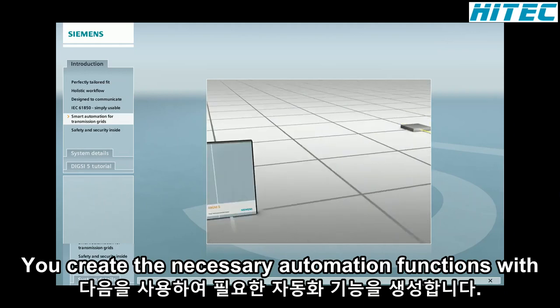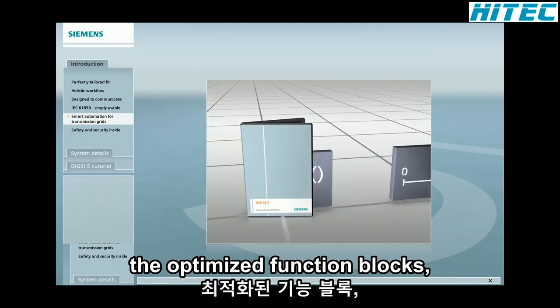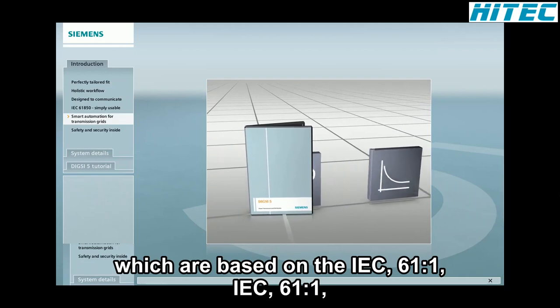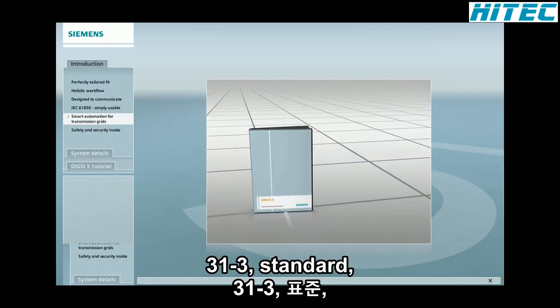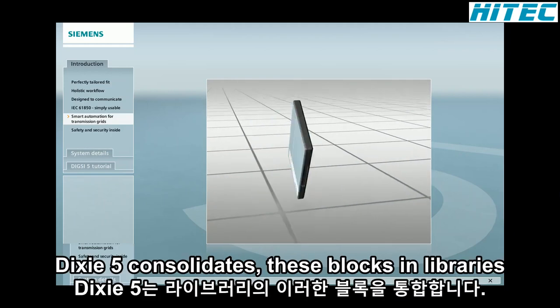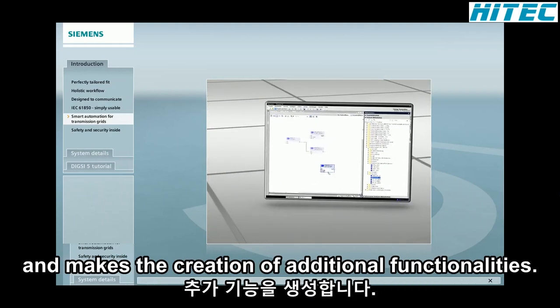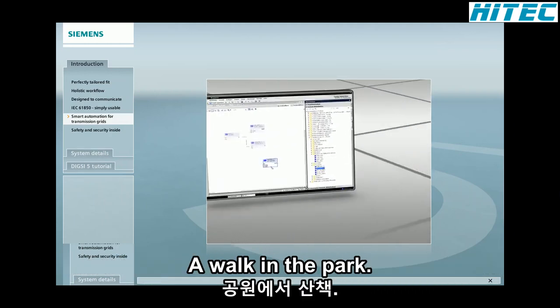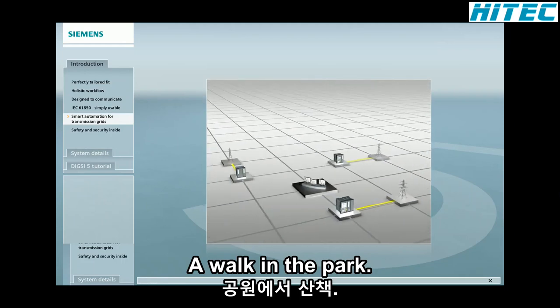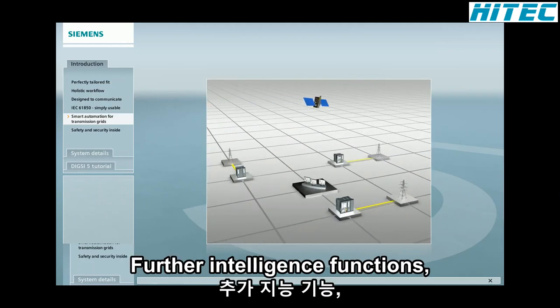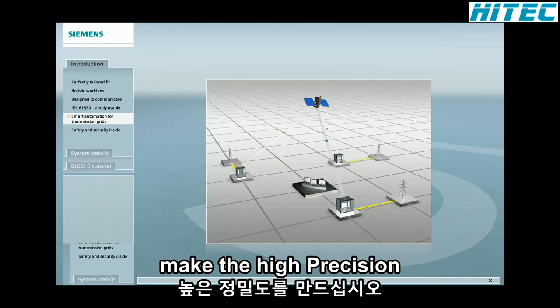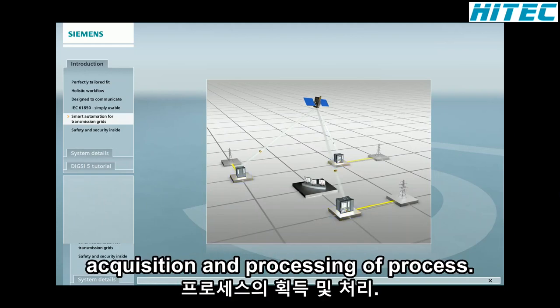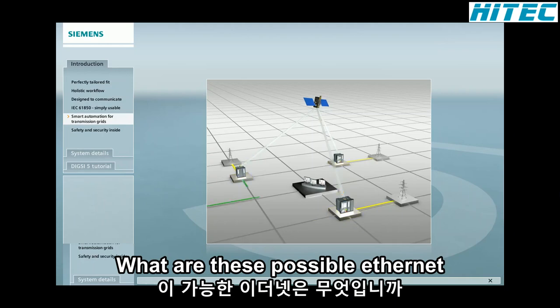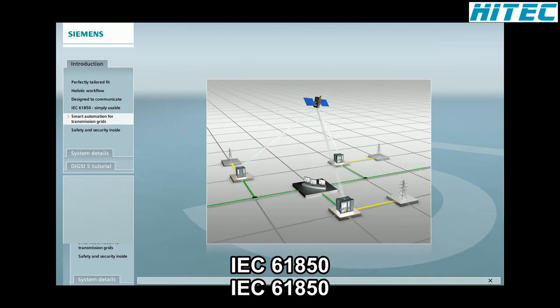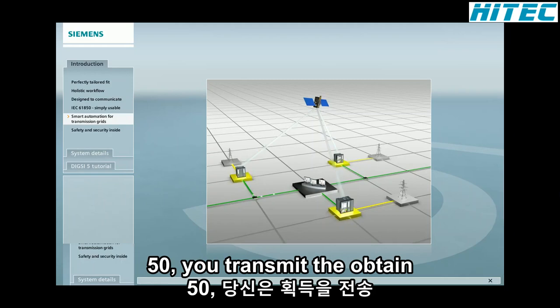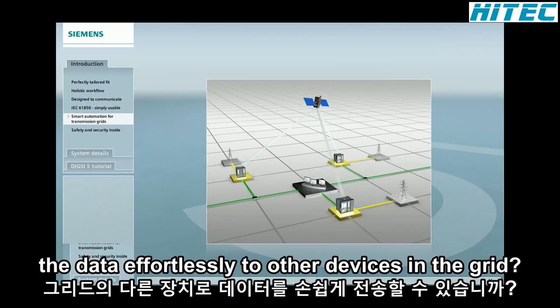You create the necessary automation functions with the optimized function blocks, which are based on the IEC 61131-3 standard. DIGSI 5 consolidates these blocks in libraries and makes the creation of additional functionalities a walk in the park. Further intelligent functions, such as the phasor measurement, make the high-precision acquisition and processing of process quantities possible. Over Ethernet and in conjunction with IEC 61850, you transmit the obtained data effortlessly to other devices in the grid.